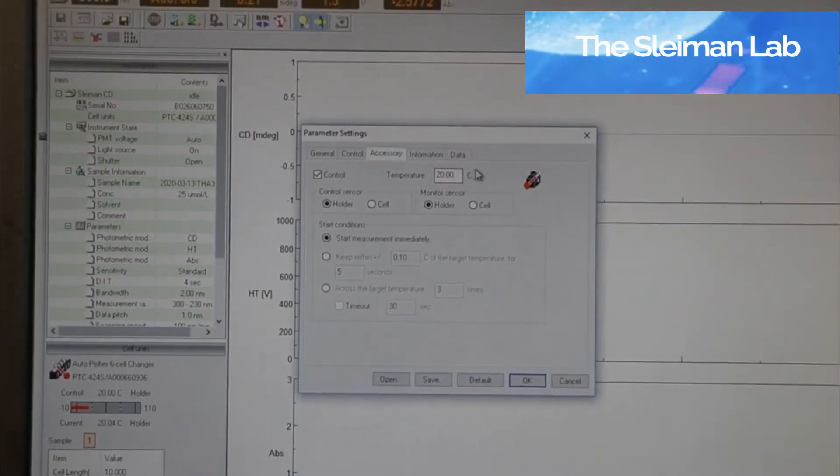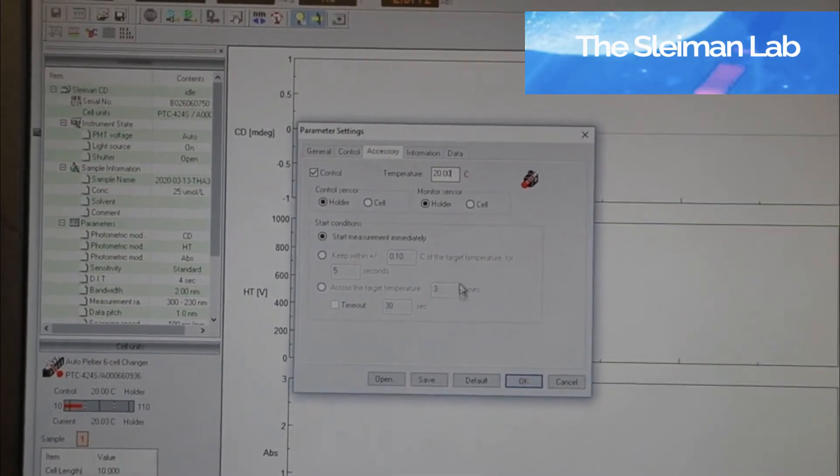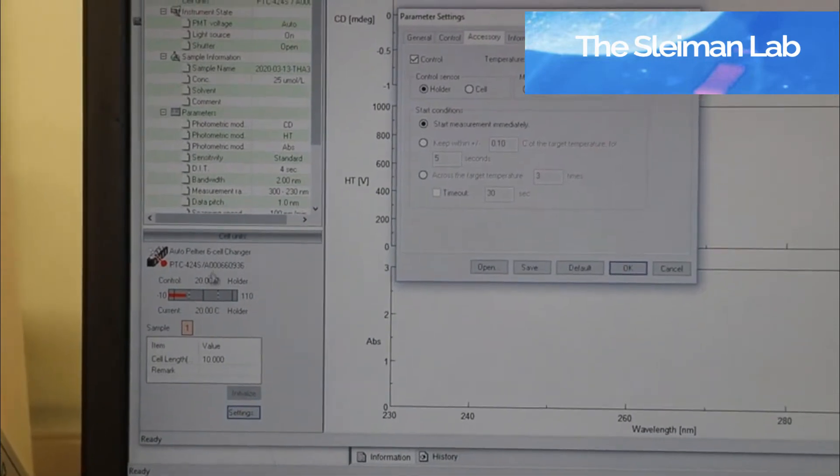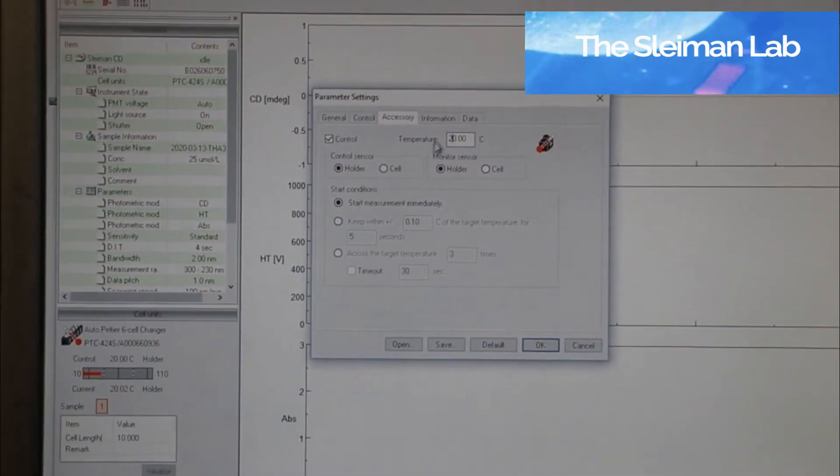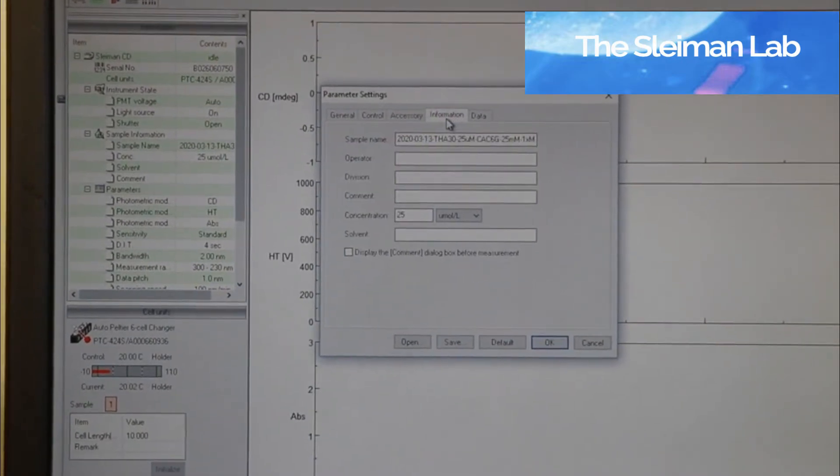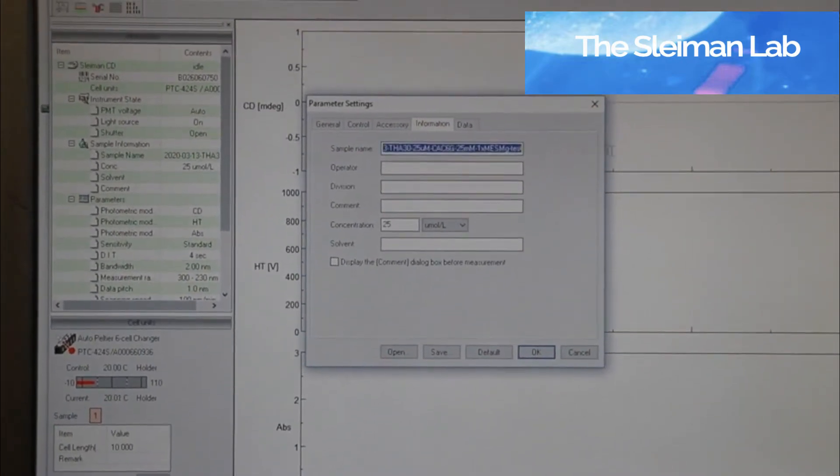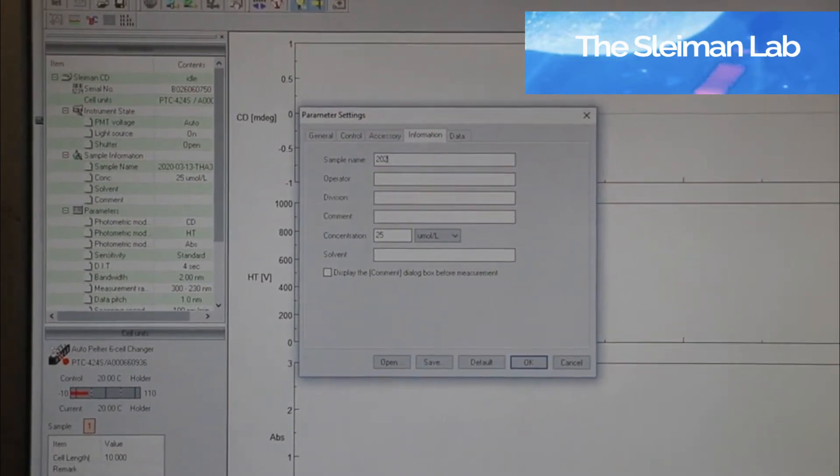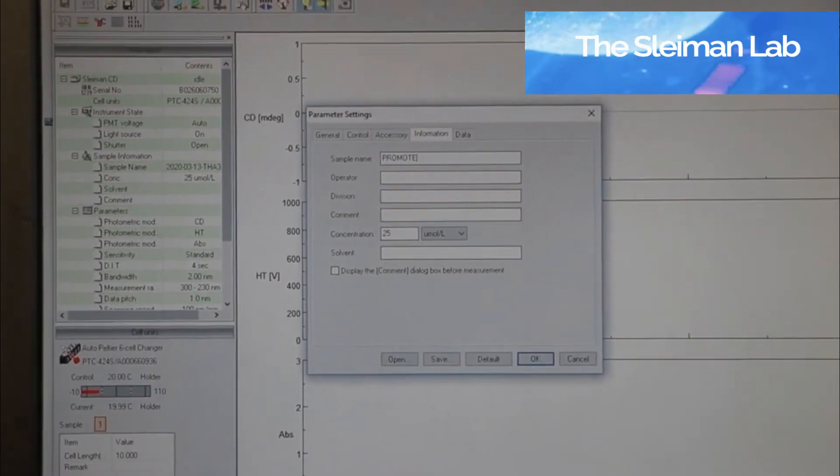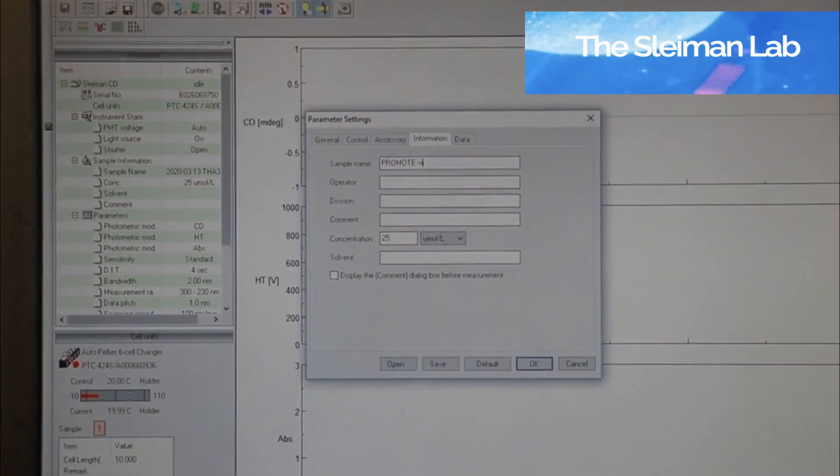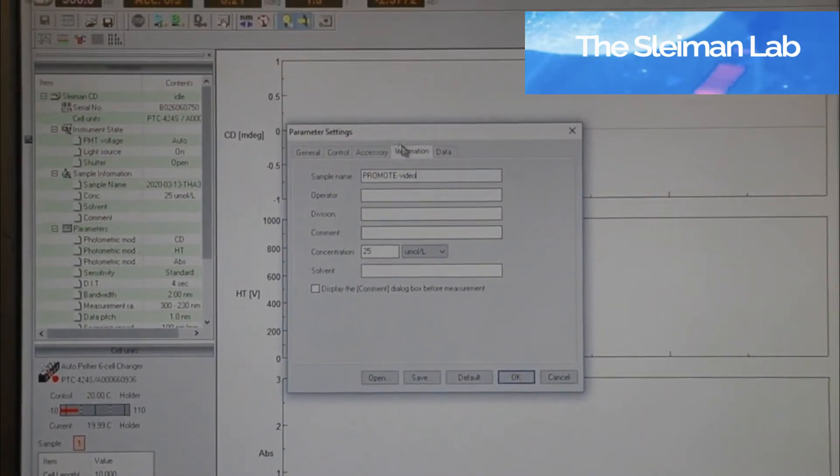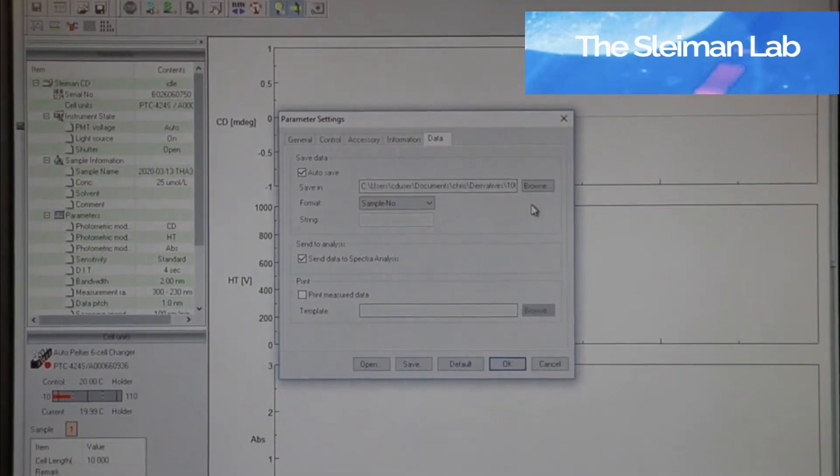The temperature at which you will be doing your experiment, which is contrary to this temperature that we've just set, this is the initial temperature, and this is the temperature the machine will go to when doing your experiment. Your sample name and where you will be storing your data.